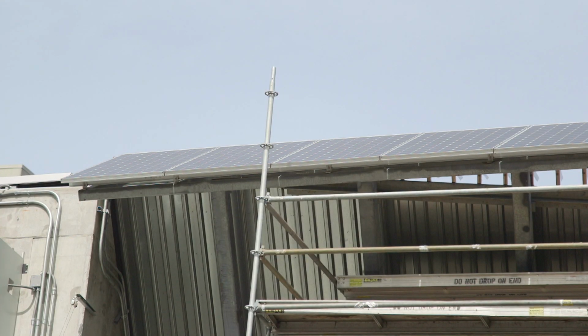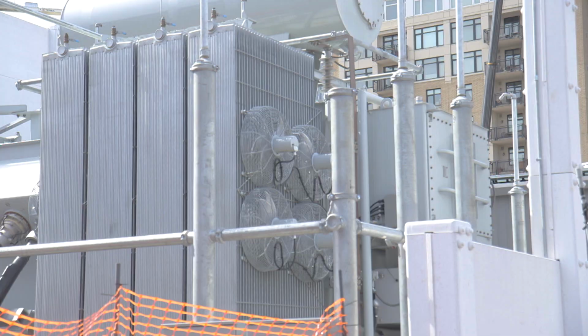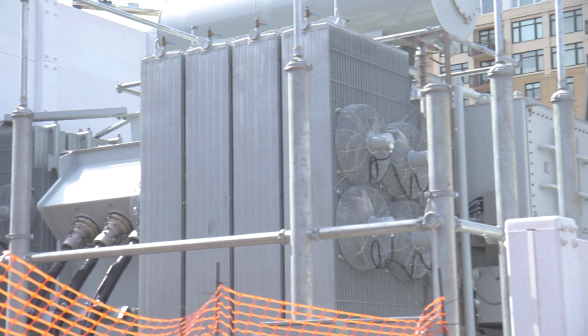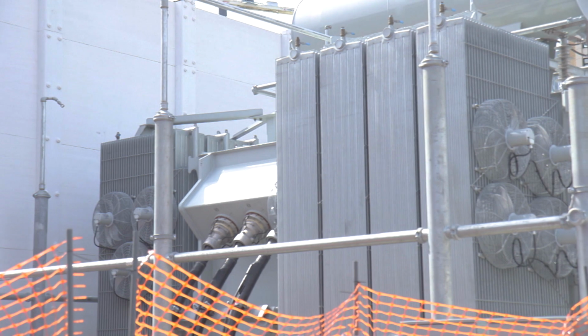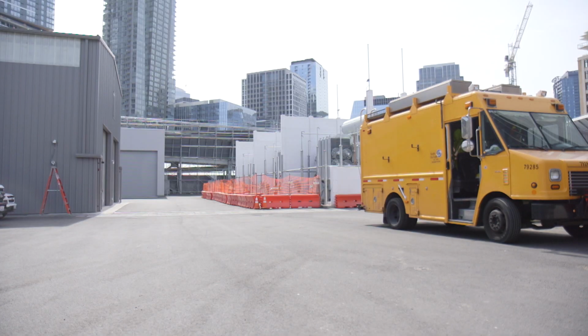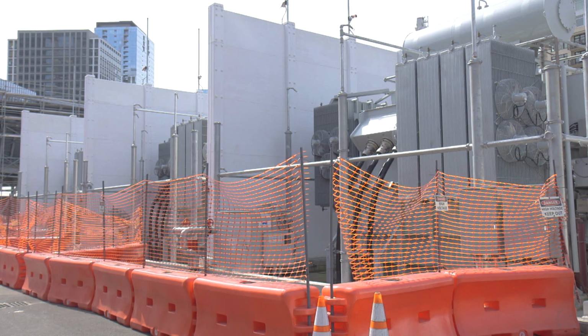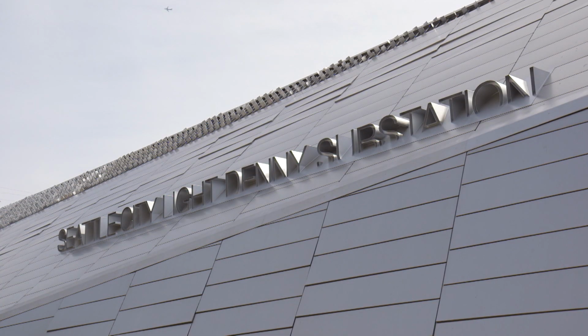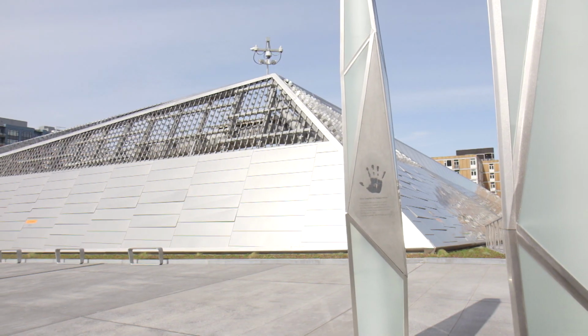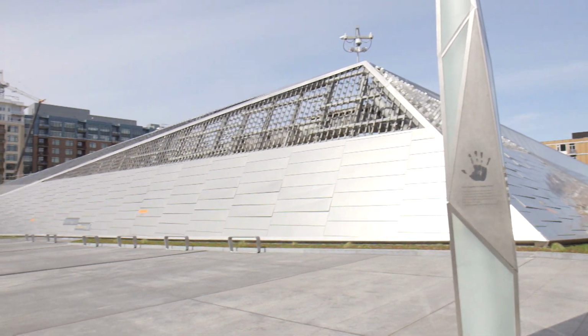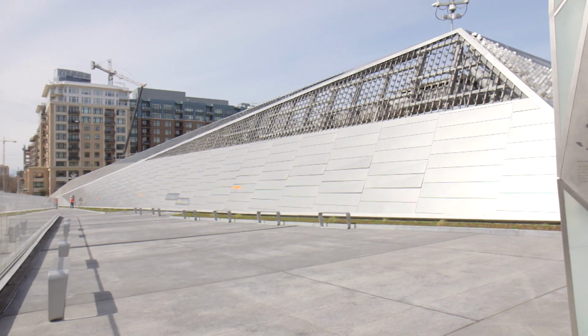Heat recovery will also contribute. Heat is generated in any transmission or transformation of power. So when the circuits are loaded and there's a lot of current flow, there will be heat generated. We're recovering that heat from the switchgear room and then piping it into the facilities. At full capacity of the substation, we're hoping that it will potentially make our community spaces net energy zero.